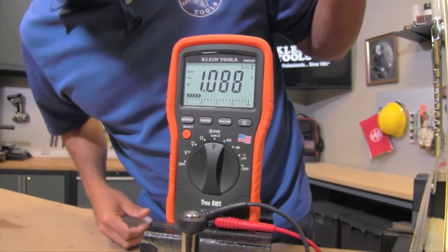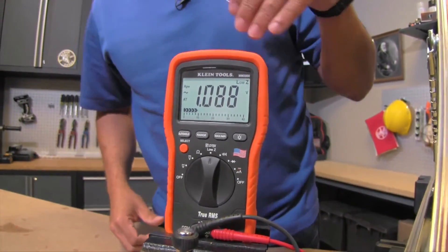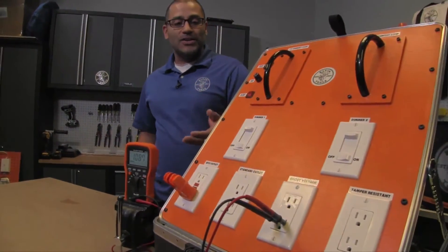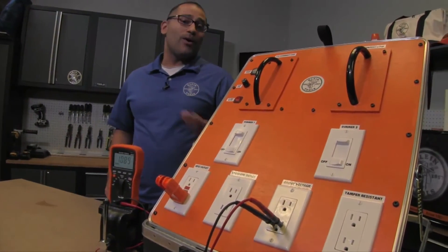And what you'll notice is out of that same outlet that was reading 109 volts you'll realize now it's down to about a volt. So this is a good indication that that outlet is somehow wired wrong or not wired at all.